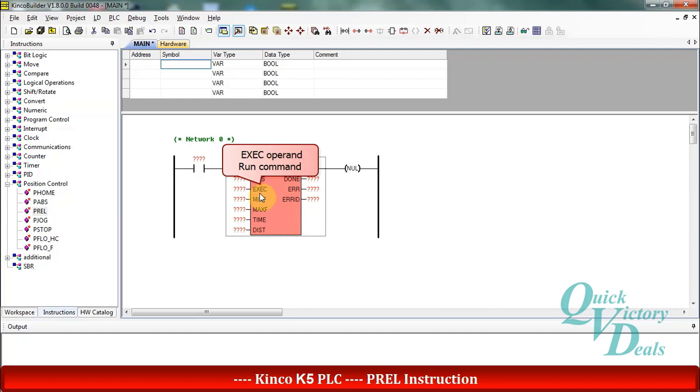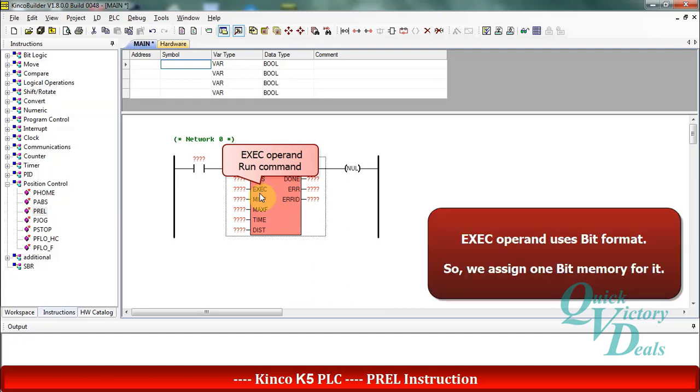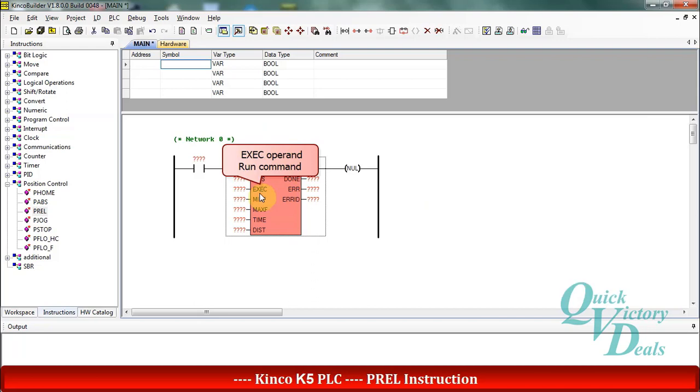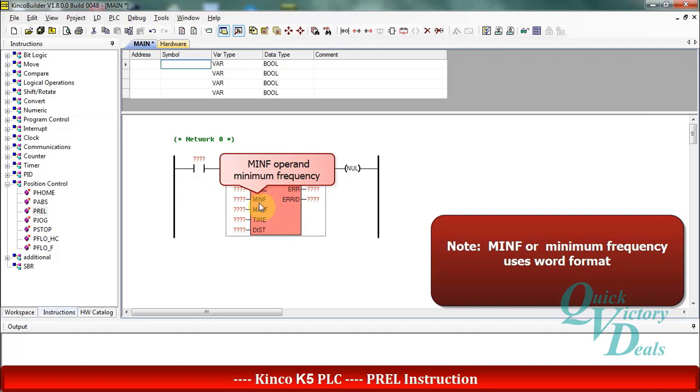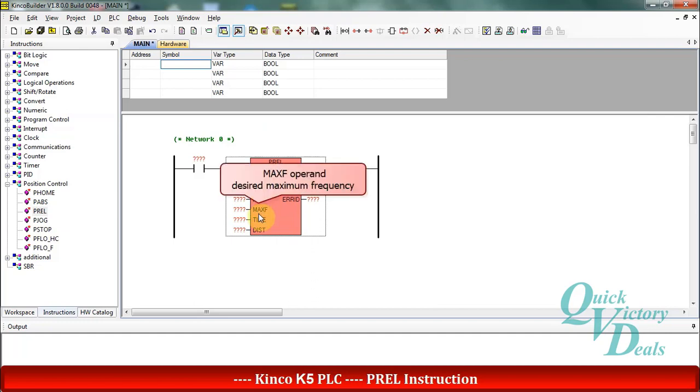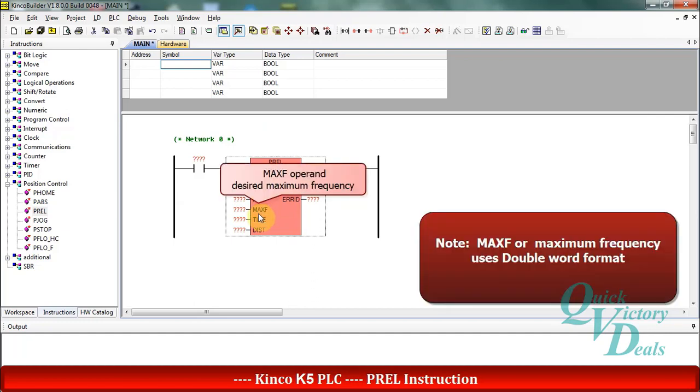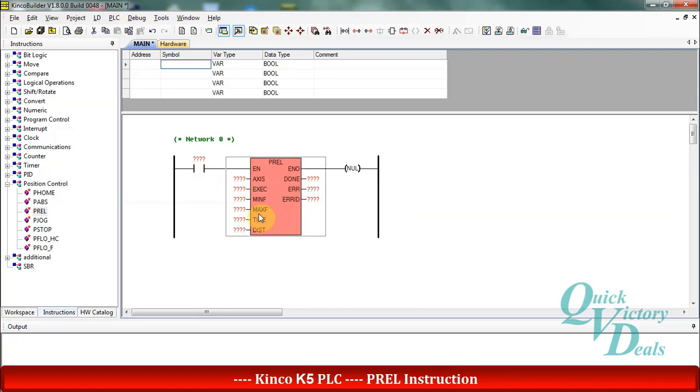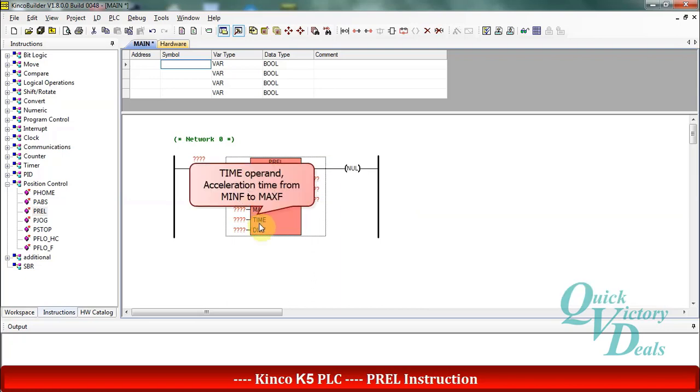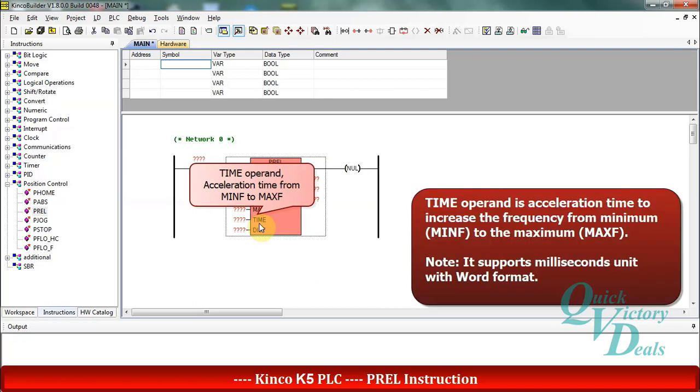In the exec operand we will use some bit memory to send the run command for the function. In the min-f operand we should select minimum frequency in word format, and in the max-f operand we should enter some double word value for maximum frequency. Then in the time operand we should enter acceleration time from min-f to max-f. It is based on millisecond and in word format.